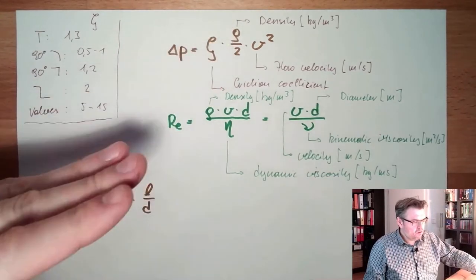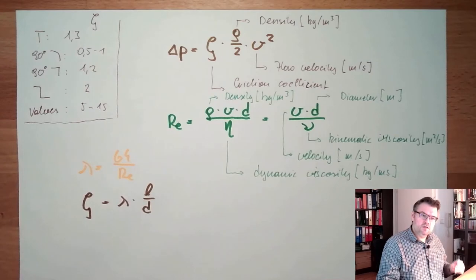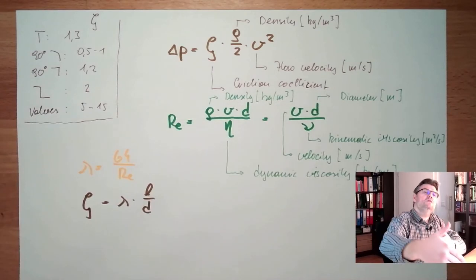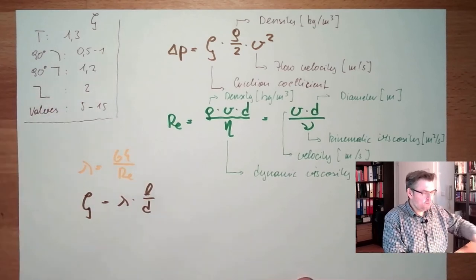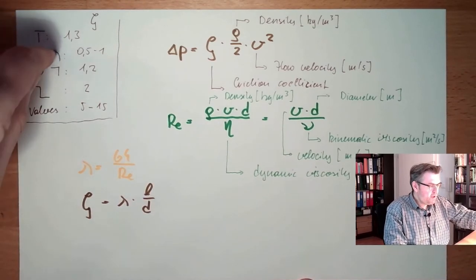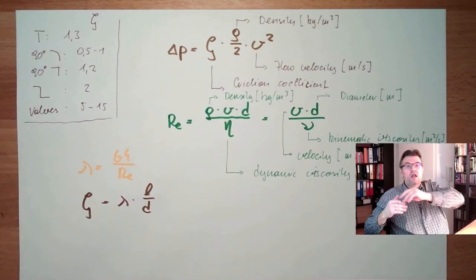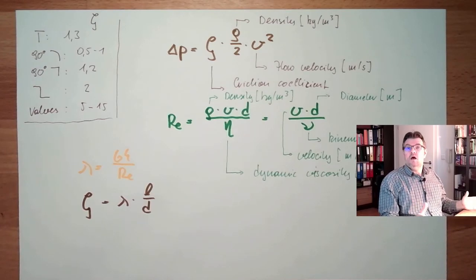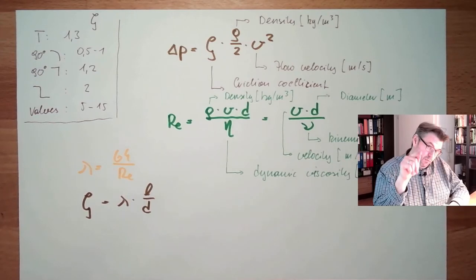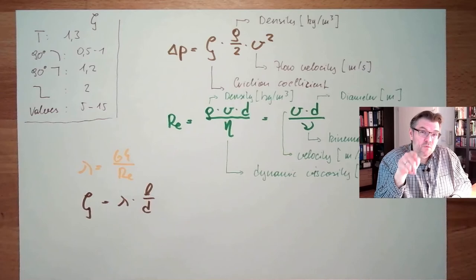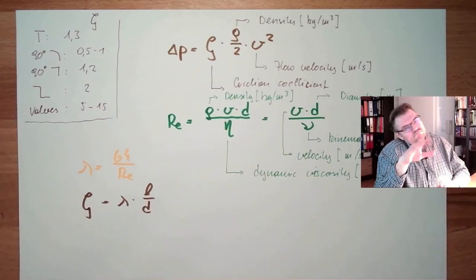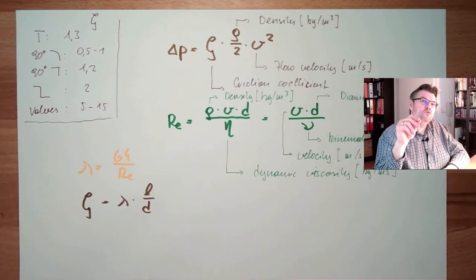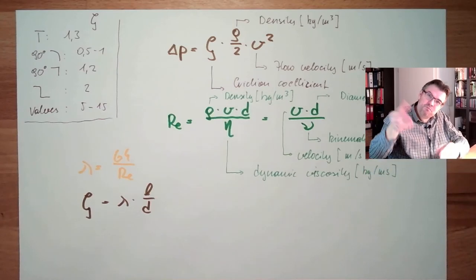In the end I have quite a lot of zeta values — I add all the pressure losses. A piece of tube this long has a certain pressure loss at a given flow velocity; a valve has a certain pressure loss; 90-degree bends have a certain pressure loss. The pressure losses along the pipe accumulate, and in the end I have a total pressure loss. If this total pressure loss is less than or equal to what I estimated at the beginning, I'm fine. If it's higher, I have to do a recalculation of my cylinder and an iterative process starts.